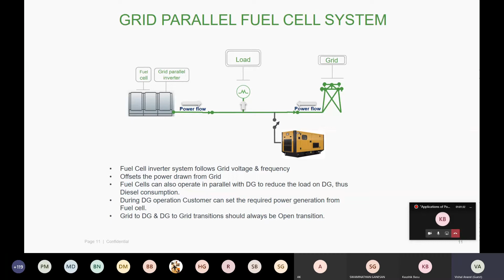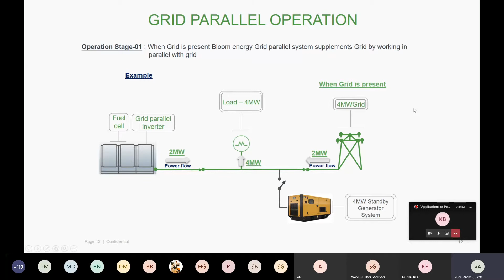So any day you would prefer this. In the grid parallel operation, when the grid is present, if it's a 4 megawatt load and our installation is about 2 megawatts, then 2 megawatts of power is generated from the fuel cell, with gas as the input, and feeds the load. The remaining power required by the load is supported by the grid. And the 4 megawatt generator is on standby.